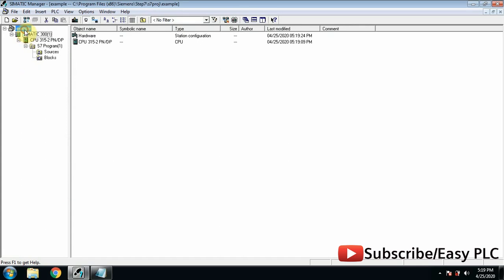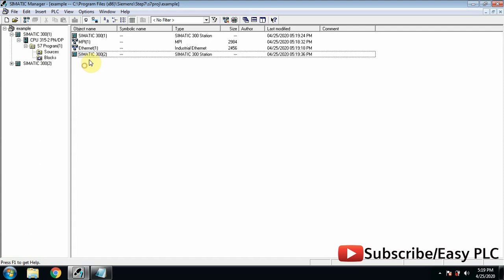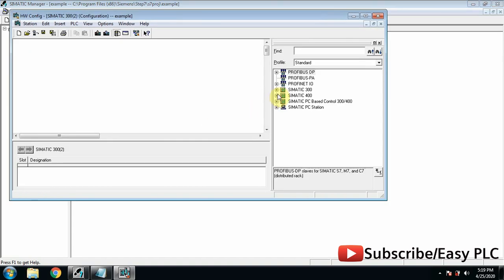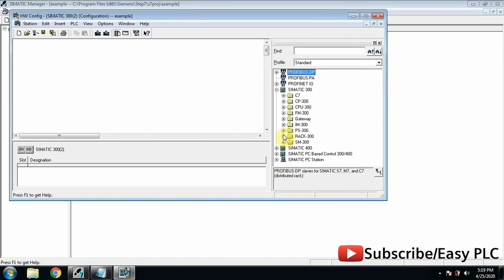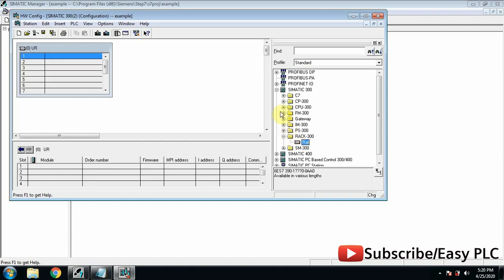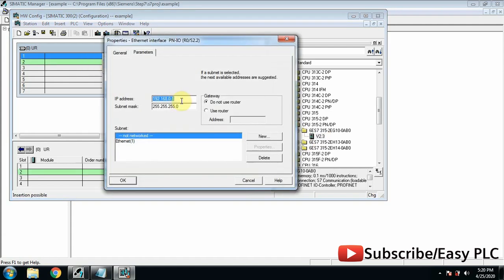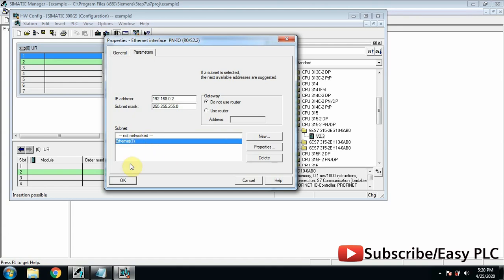Now we will add another S7300 station and this will be the remote station. As we did earlier, go to the hardware configuration and add the 315 PLC. We will change its IP address because local and remote PLC stations should have different IP addresses. Select Ethernet communication and click OK.